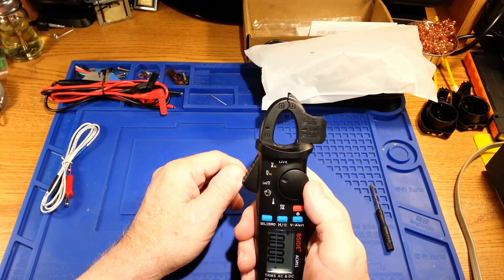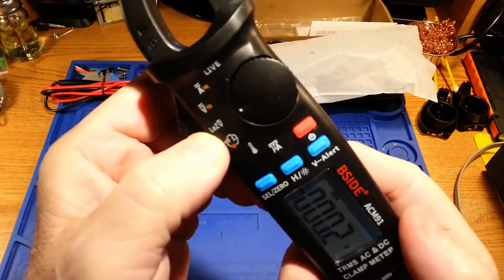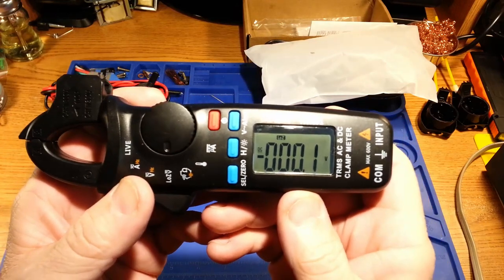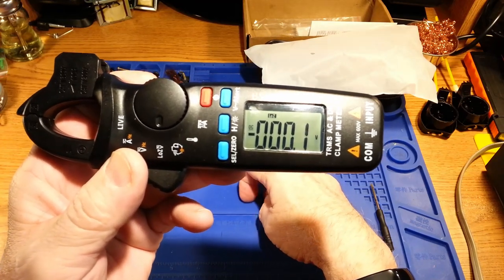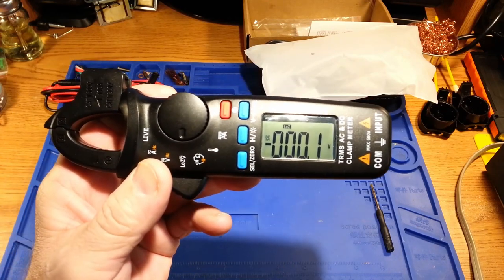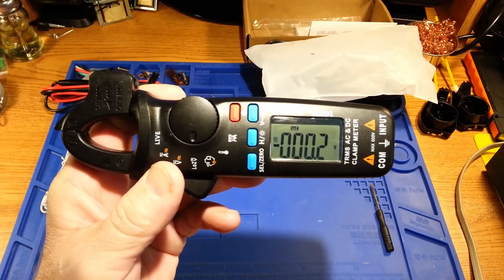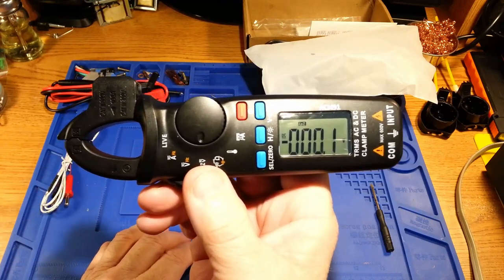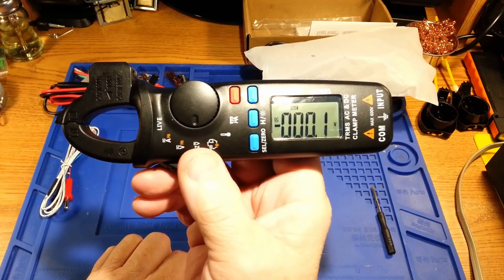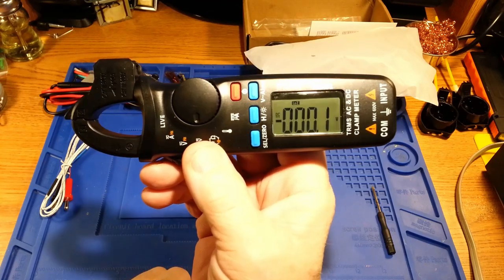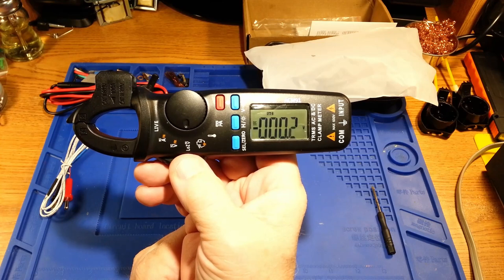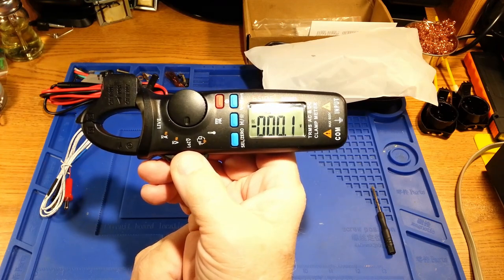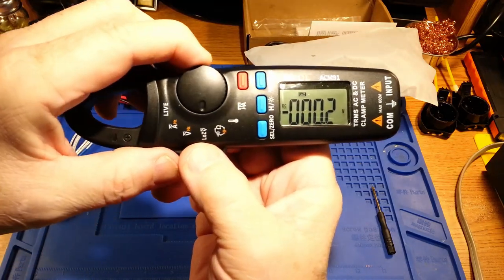One thing for functions outside of the current range is it's advertised as having a low impedance AC/DC volt function. The AC part of that is nice for people that do household wiring because you will find times where you have induced AC voltage onto a disconnected lead. A meter that's got a really high impedance will detect that as a stray voltage, but if you can bridge something with lower impedance it'll drain off that voltage and give you a better indication of the actual voltage potential of that wire.